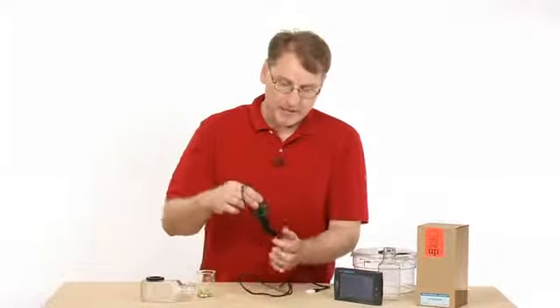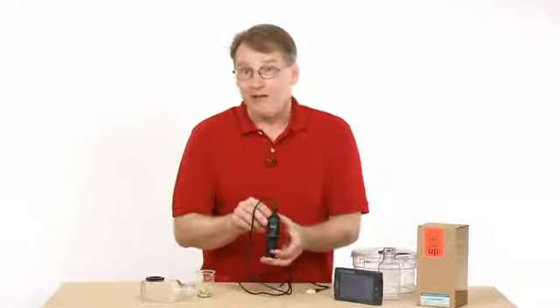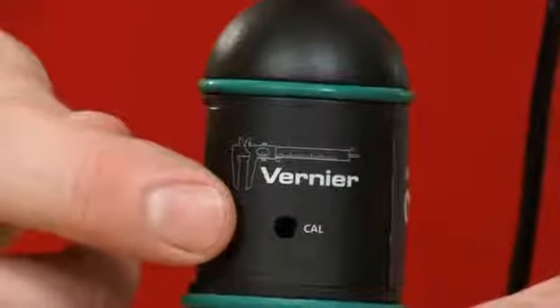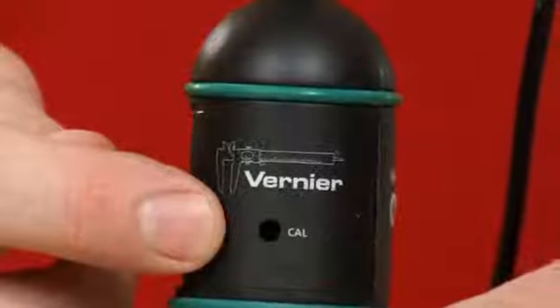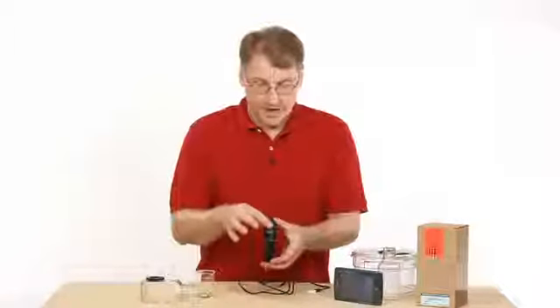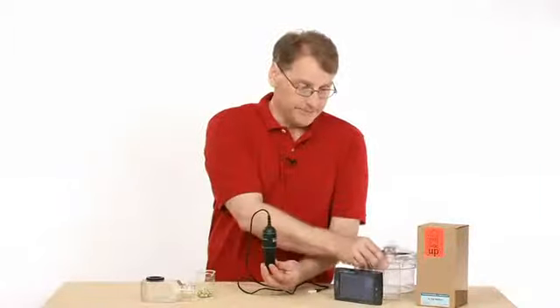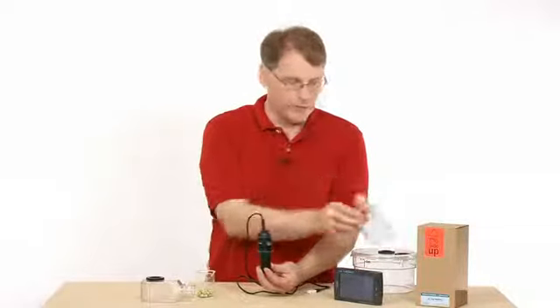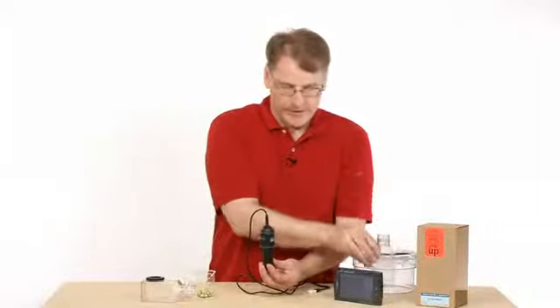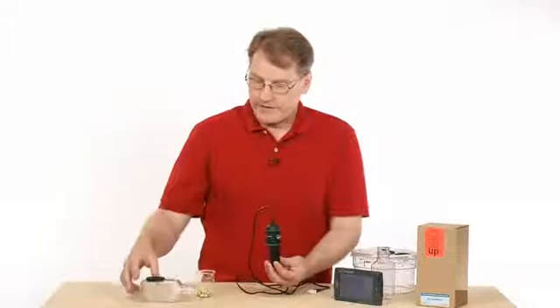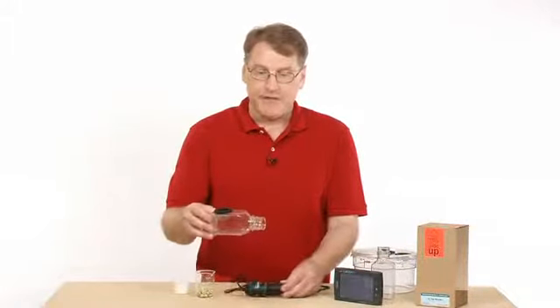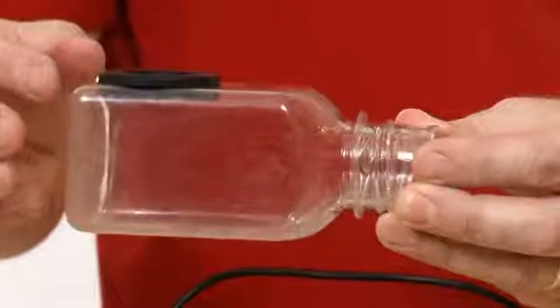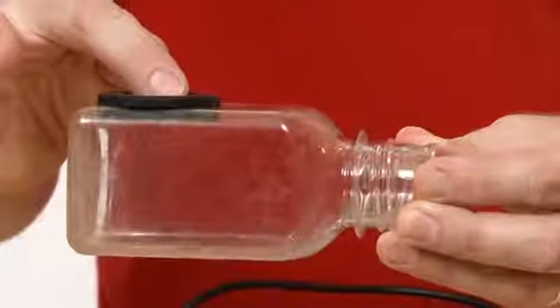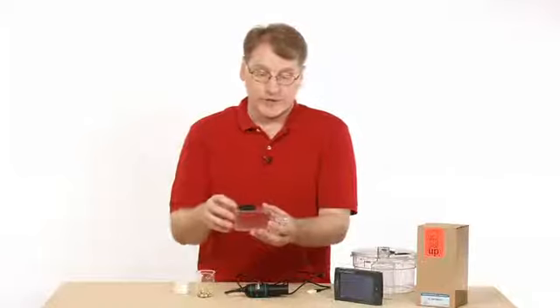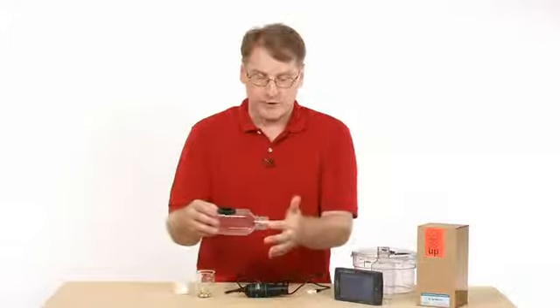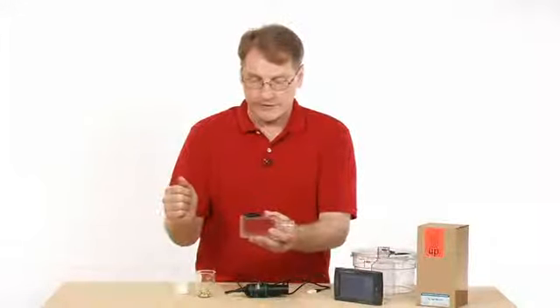It is possible to calibrate the sensor, though you probably don't have to. The sensor booklet will tell you how to go about doing that. Now, the oxygen sensor comes with a Nalgene bottle, and so this bottle here is the standard one, would be in there. And so it comes with that one. Another option, though, is the BioChamber 250, and so this is the Nalgene bottle with an extra hole for a sensor to go in here. You might use this in conjunction with the CO2 sensor, so you could put the CO2 there and the oxygen in there if you wanted to.